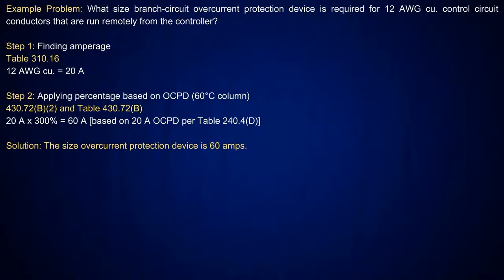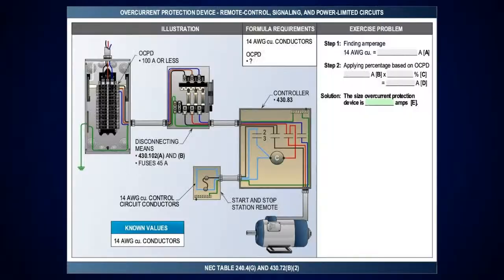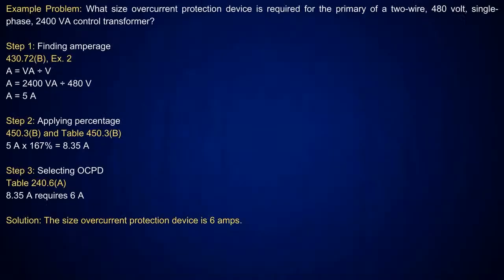Right. Okay. And this is just a verification. The information's already in the table. All we're doing is showing you below the table and the percentages. How did they make that determination? This is how they did it. Okay. And then you'll see here we have the control circuit conductors run remotely over here. And then you need to use table 310.16, 60° C column, take it at 300%, and then size your overcurrent protection device accordingly.